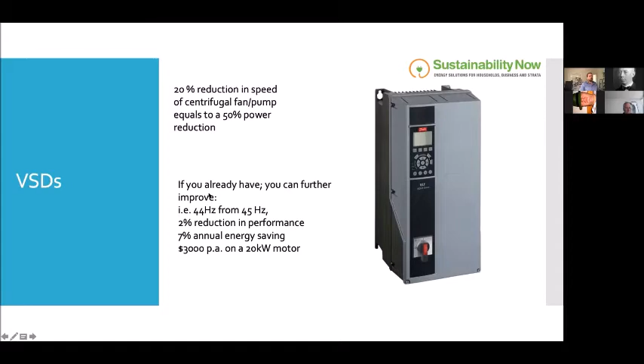That's what makes it really great, you get disproportionate power savings. So here's a little example: the difference between 44 hertz and 45 hertz on a motor is only a 2% reduction in speed, but it can result in a 7% reduction in energy use. That works out to about $3,000 a year on a 20 kilowatt motor. So just 1 hertz can make that much difference.